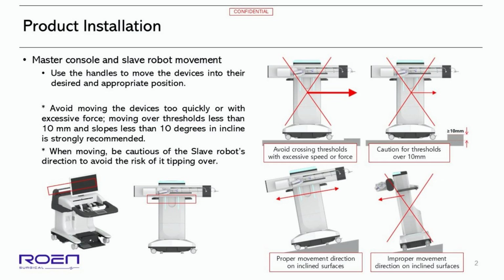To set up the system, the master console and the slave robot must be moved. Use the handles to move the devices into their desired and appropriate position. Avoid moving the devices too quickly or with excessive force. Moving over thresholds less than 10 mm and slopes less than 10 degrees in incline is strongly recommended. When moving, be cautious of the slave robot's direction to avoid the risk of it tipping over.